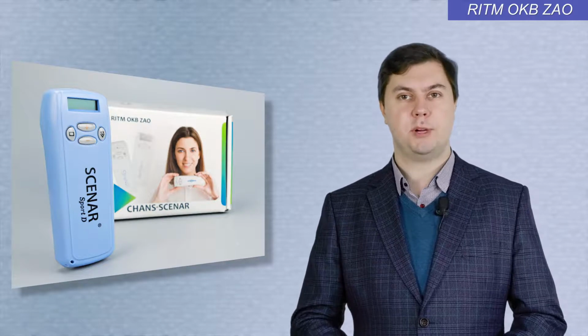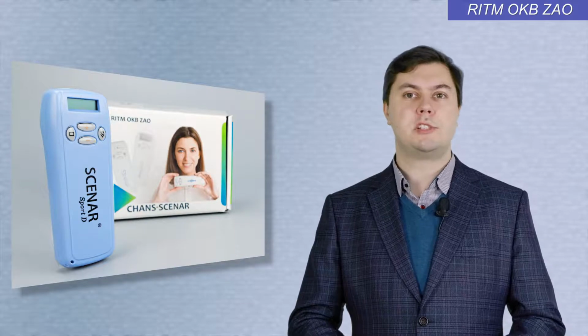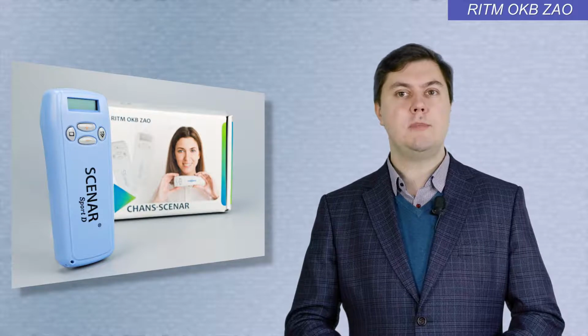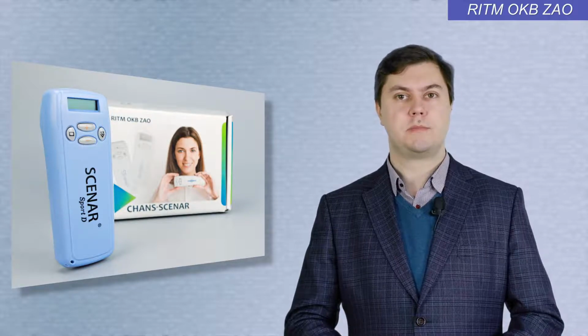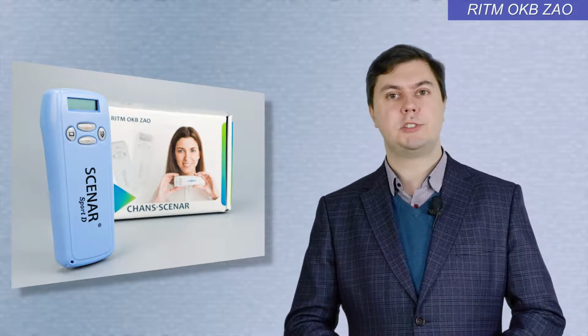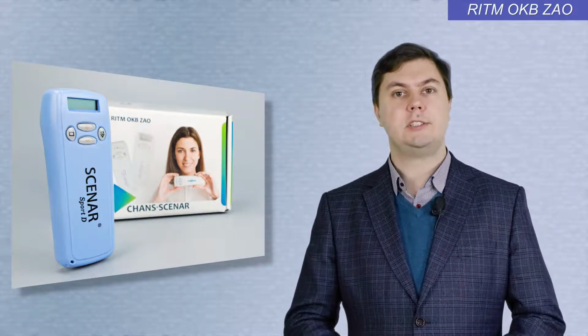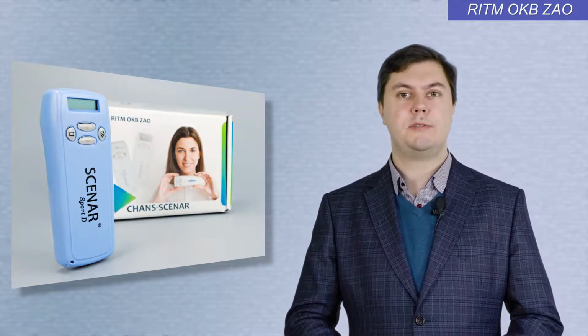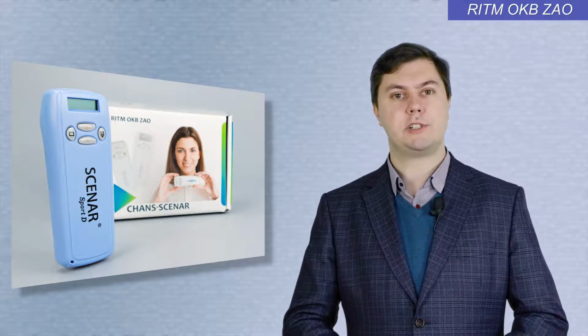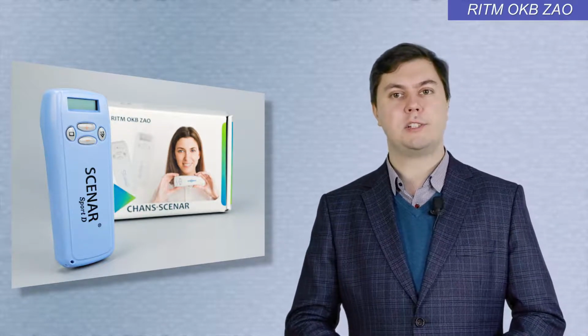First phase is the bio mode. The treatment is done with the batches of pulses. The number of pulses in a batch and the gap between the pulses are controlled automatically, depending on the impedance of the interelectrode tissues. The stimuli rate is set automatically between 15 and 340 Hz, according to the preset's program. Second phase is the low-frequency treatment. Third phase is the mid-frequency treatment. And fourth phase is the high-frequency treatment. You can control the treatment energy level in all phases of this preset.